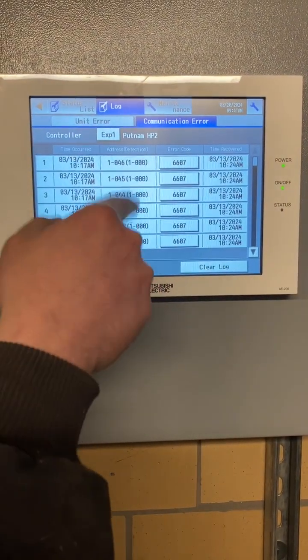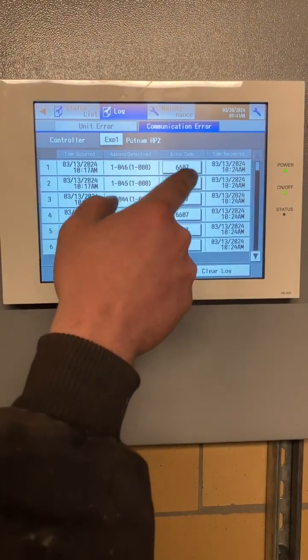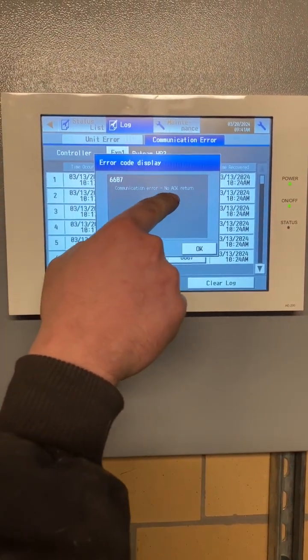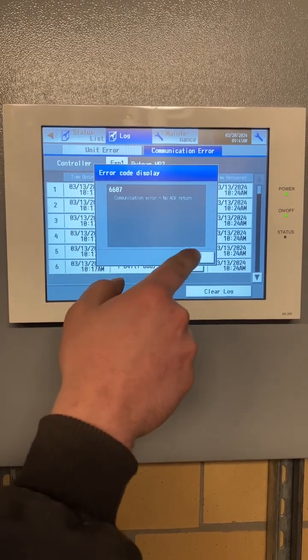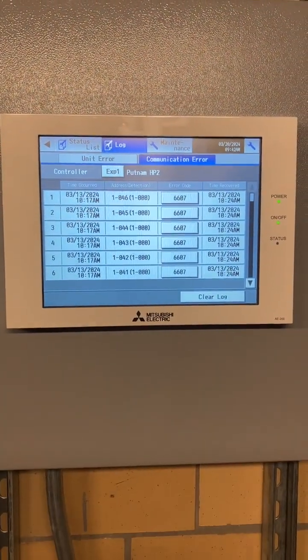So these are all communication errors, probably from when they dumped the building. 6607, so it's a communication error, no acknowledge return. That came through on 313. They were doing a bunch of generator tests, so that comes through when they shut the power off and turn it back on.